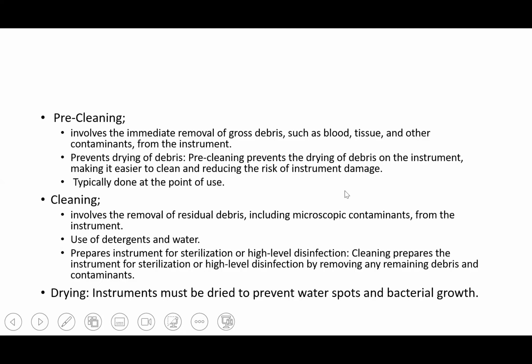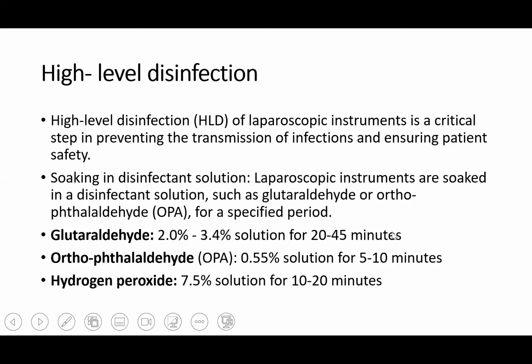Now, after these first two processes, then you have to dry. The instrument must be dried to prevent water spots and bacterial growth. Now, high-level disinfection, we already defined all these. High-level disinfection of laparoscopic instruments is a critical step in preventing the transmission of infection and ensuring patient safety. Now, soaking in disinfectant solution. You see, after that drying, you have to soak. Laparoscopic instruments are soaked in a disinfectant solution, such as glutaraldehyde or ortho-phthalaldehyde, which is OPA, that is Cidex, for a specific period.